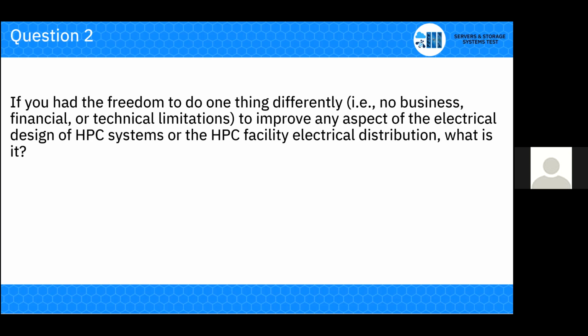I've reused underground conduits, and now I'm having to run things overhead and exposed, with a downstairs mechanical space and the computer room upstairs. Downstairs I'm putting in medium voltage, 13.8 kV. All the transformers and switchboards eat up everything along with the large conduits, and that leads to issues with available fault currents being very high, requiring current limiting devices to help limit that. Everything takes up more space, that's one of the issues I have right now.